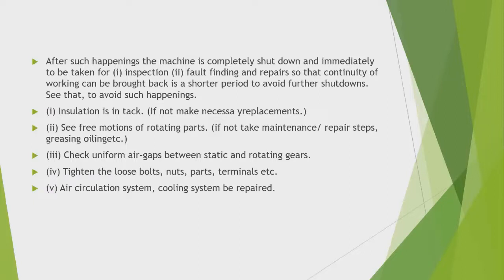To avoid such happenings, see that insulation is intact; if not, necessary replacement is required. Check free motions of rotating parts; if not, carry out maintenance, repair, greasing, and oiling. Check uniform air gaps between static and rotating parts.